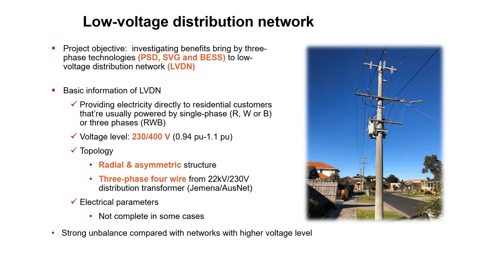There are three phases, and in this particular example in Australia, in two suburbs in Victoria, the nominal voltage level is 230 volts single phase or 400 volts three phase, with a preferred range between 0.94 and 1.1 per unit. It's a radial structure and asymmetric structure, a three phase four wire system.